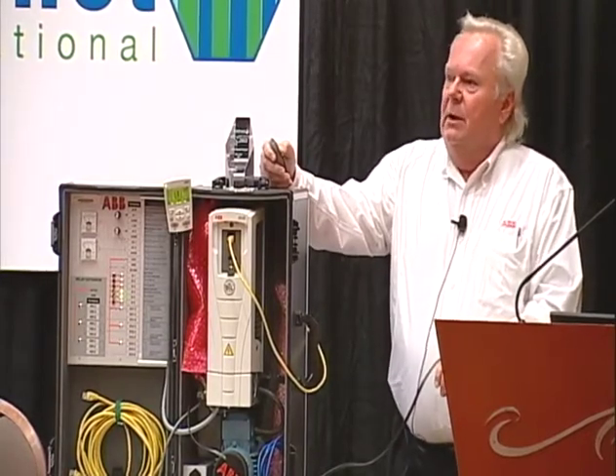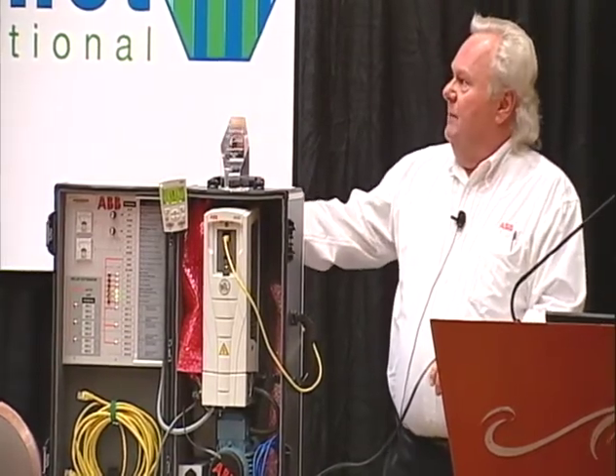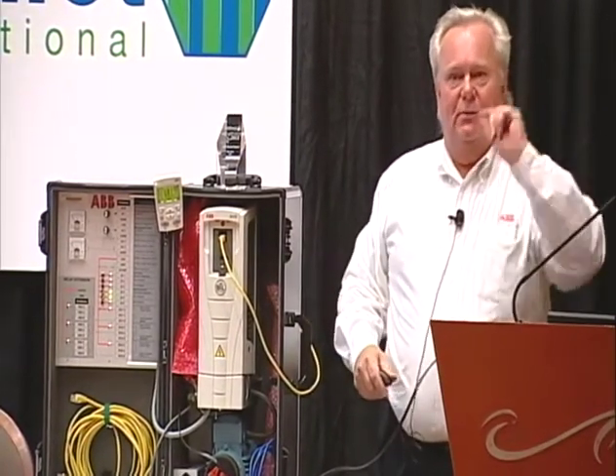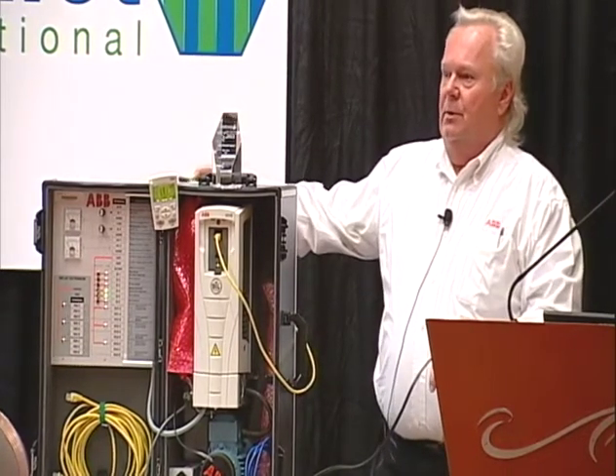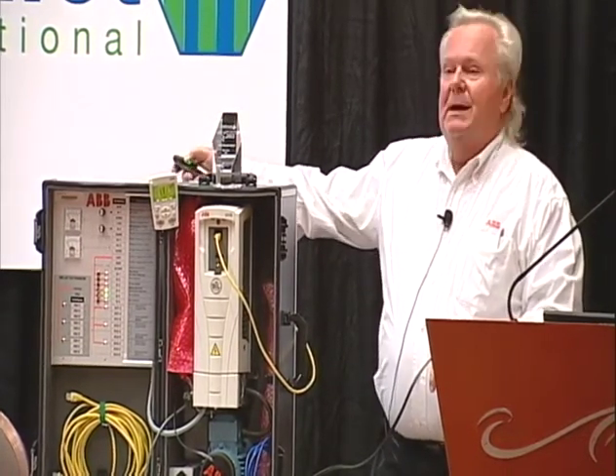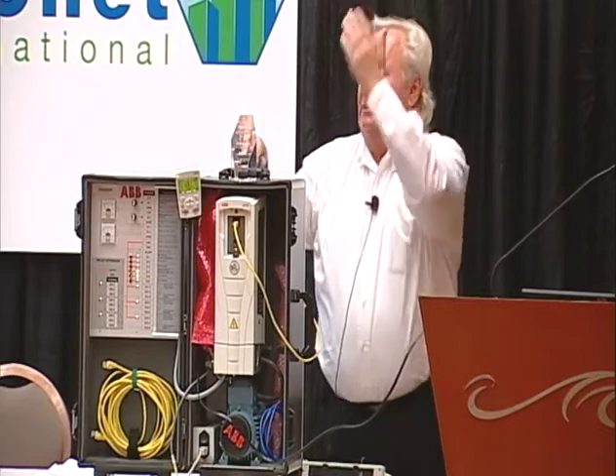So what I've done is I've wired an output from the VFD that whenever I call for a run from the VFD, the first thing I'm going to do is fire a relay. That relay is connected to the damper actuator. It tells the damper to open. When it gets all the way open, the damper end switch is wired back to the VFD, says proof, I'm open, I've got my path of flow now, and we start the fan.